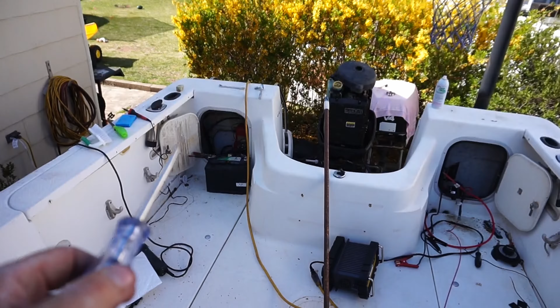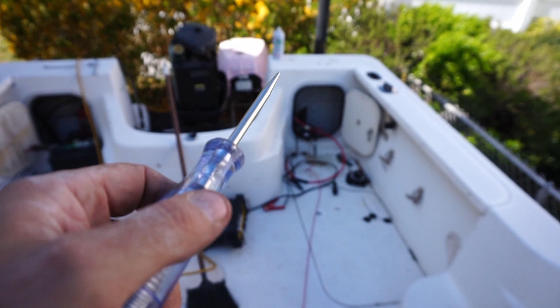So what we did was get the switch hooked up to the battery on the other side, got the ground here, and wired my test light. Thinking out loud: battery's grounded, connected to the switch. The switch is powered to the circuit breaker, power is going to the circuit breaker. There's a power lead from the circuit breaker that should work its way all the way to the front here, to my positive bus bar. So if this light goes on when I touch it to that positive terminal, that means I have power running from the circuit breaker to the bus bar.